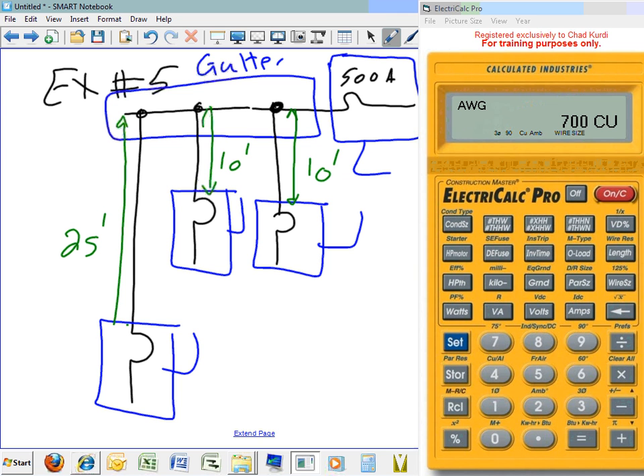You know what I'm talking about here? It's the distance between the circuit breaker, this equipment, and this equipment, basically. We don't go right inside the equipment, but between the 2 equipments. What's the difference in the distance, or why the 10 versus the 25? The code has 2 rules, based on 10 or 25 feet, and they allow you to use a smaller or bigger conductor. That's the only difference. You're going to see in a second here. Okay, any questions about this?